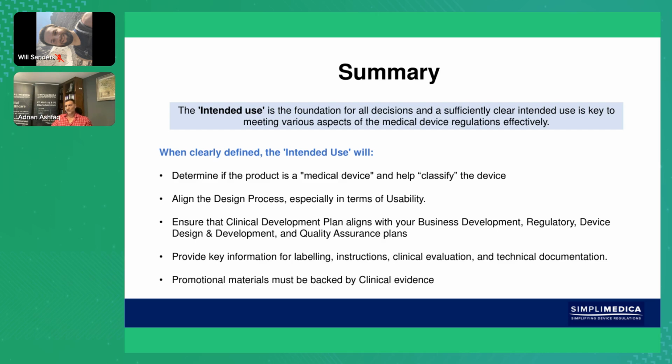And then don't forget your quality management system. If you end up saying something in your intended use which wasn't covered by your ISO certificate, it could be in the installation, the servicing, or any one of those other clauses. Sterility, for example: we've got 3 or 4 clauses in ISO 13485 to do with sterility. We've got a problem if we say that these are non-applications, but they are applications because your device is sterile. We've got to make sure we've got that correct as well.